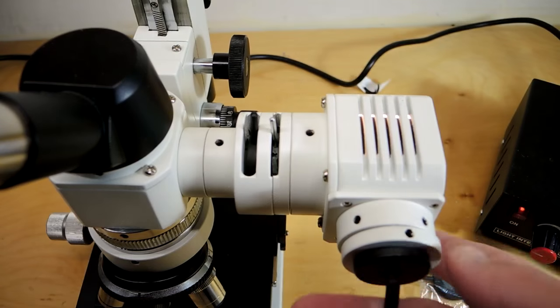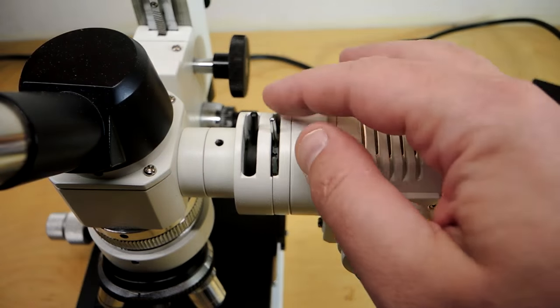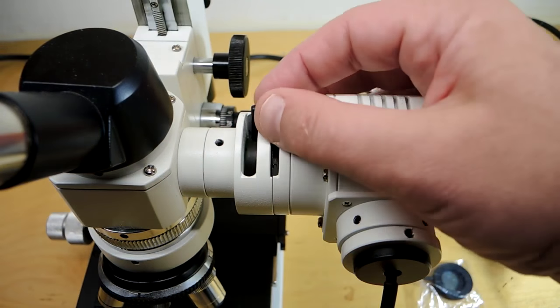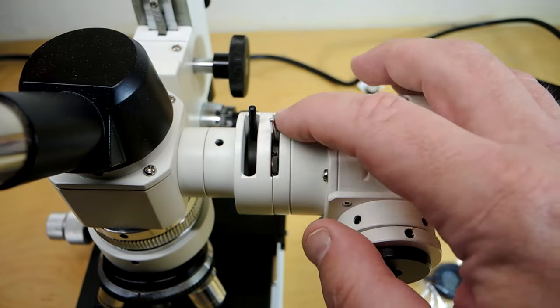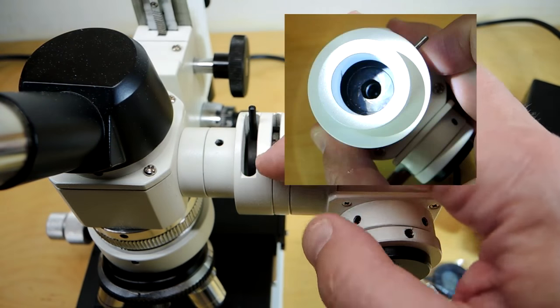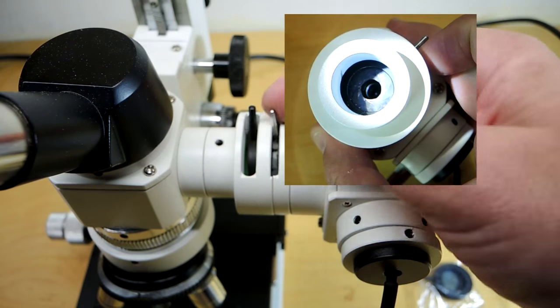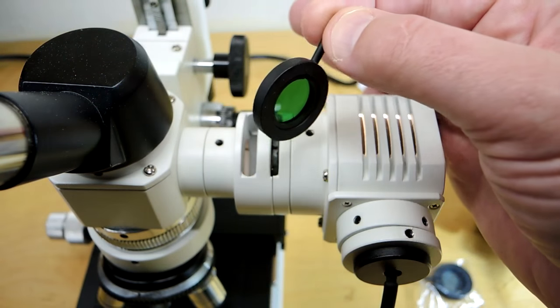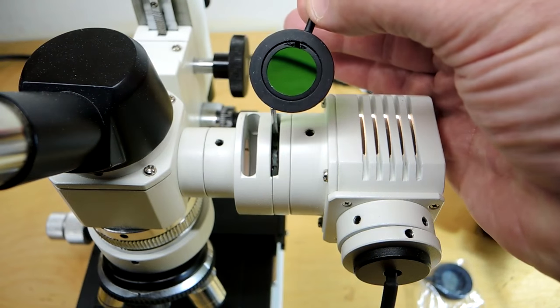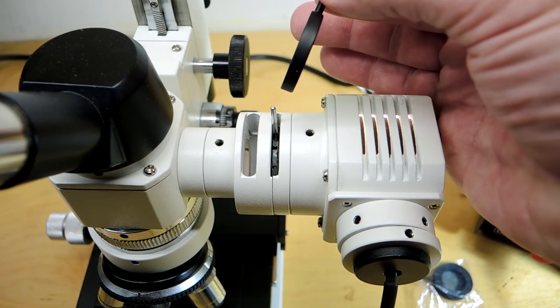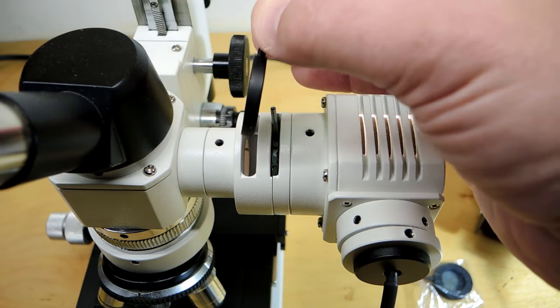So this is the illuminator. As I mentioned, there's a halogen bulb inside here. And there are two adjustments, and this one here adjusts the amount of light that goes in. There's a little aperture, and let me just insert a picture of it moving back and forth. And then there's also a slot here for a filter, and it comes with a number of filters. One's green, one's a polarizing filter, and one I think is something called a neutral density filter.